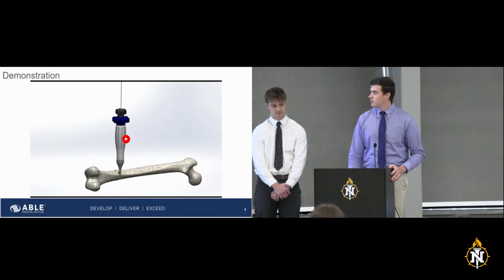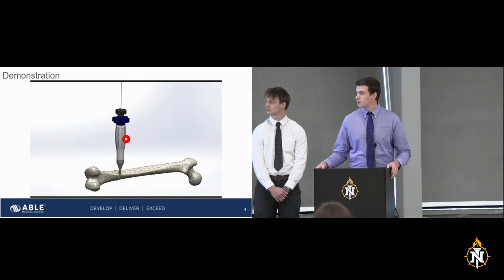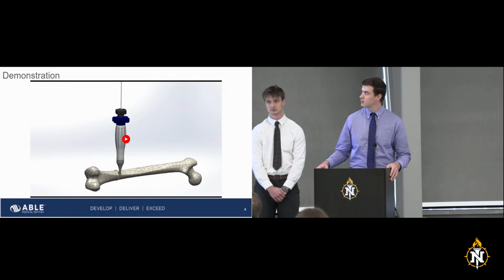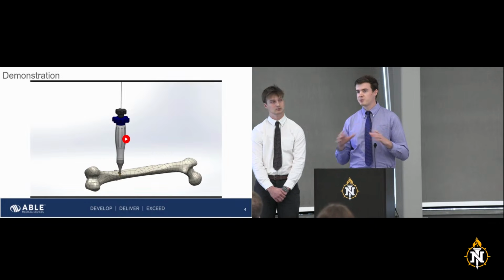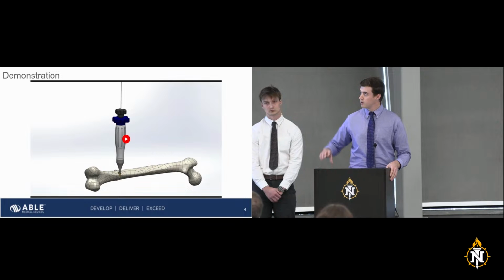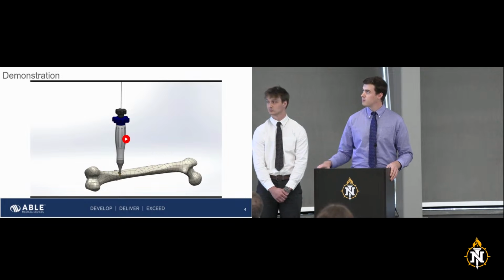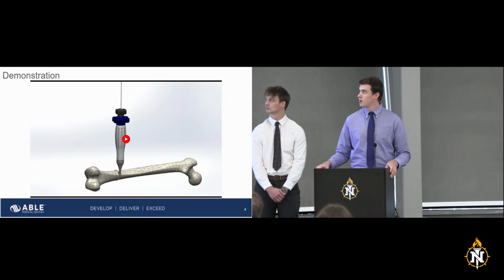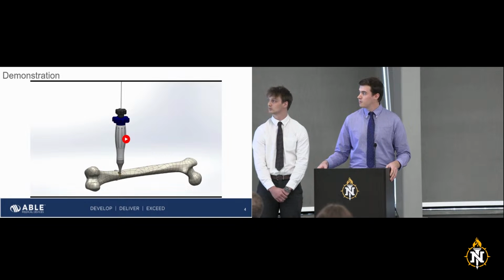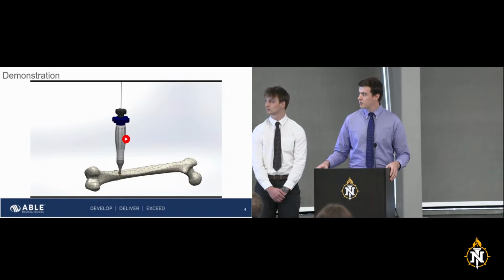So we've got a quick video of the insides of our product. You'll see an exploded view of how everything goes together and what the insides look like. A few things to note: the top knob in the gray is our collet tension knob. When you turn that, you're basically compressing a collet, which clamps around the cable. The blue knob is our tensioning knob, which turns an Acme screw internally. That results in a direct linear motion, so there is no twisting of the cable, which is something we wanted to avoid. And then to set the final set screw on the implant, you just turn the entire device as if it's a screwdriver.